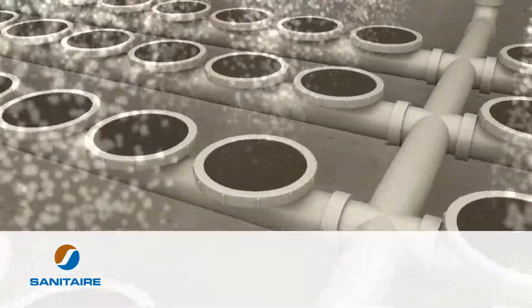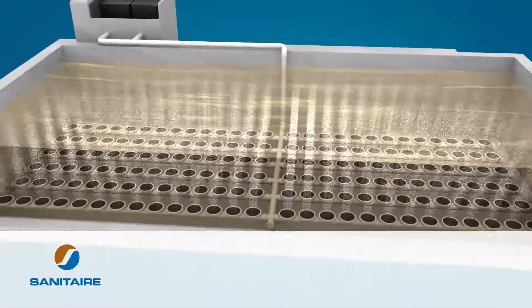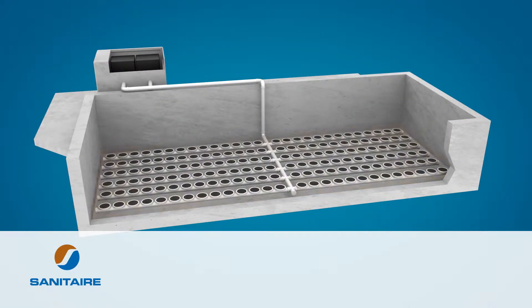In order to maintain peak performance, if you continually see large boiling areas or dirty water during moisture purging, Sanitaire recommends that you drain the tank for a complete inspection of the system components.